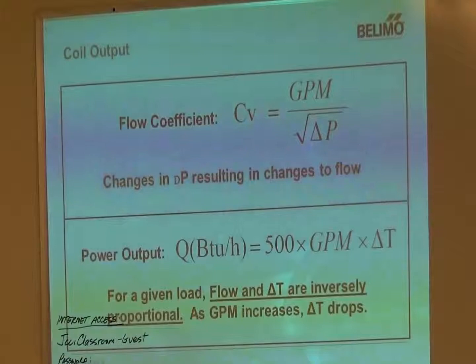We'll talk about why you might want to do that. Why am I going to spend all this money on all these extra goodies and run it as a pressure dependent valve? We'll talk about that. But yeah, this is the formula that Brian was referencing, the power output formula, and that's why we're still using the GPM and the delta T, even when we're talking about controlling based on power requirements.